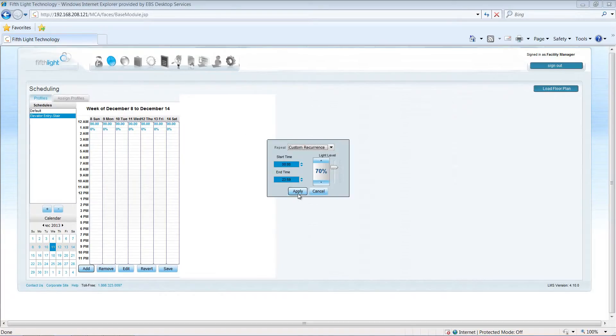Back in the main transition window, I'll type in the desired transition time. For our schedule, I want to transition the lighting to turn on to a 50% light level at 7:30 in the morning. Lighting should transition back to off at 6 o'clock in the evening.